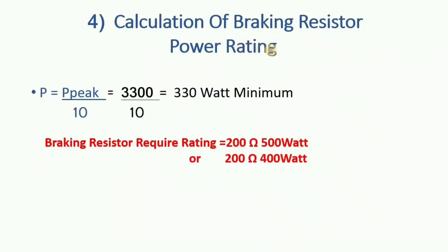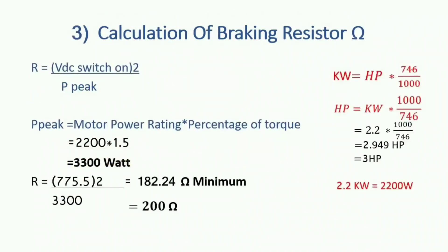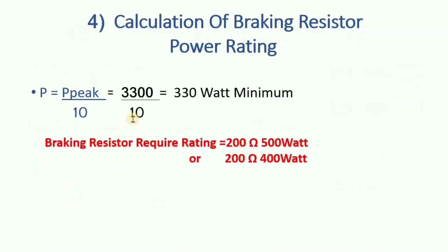Now the calculation of the braking resistor power rating. The formula is: P = P_peak ÷ 10. We found the peak power is 3300W, so 3300 ÷ 10 = 330W. As this may be an odd value and not available in the market, we can use a 200 ohm, 400W or 500W resistor.